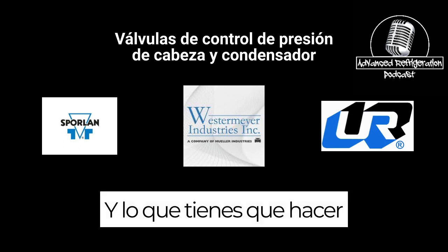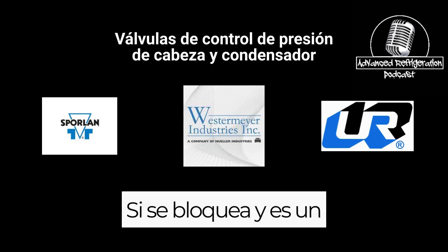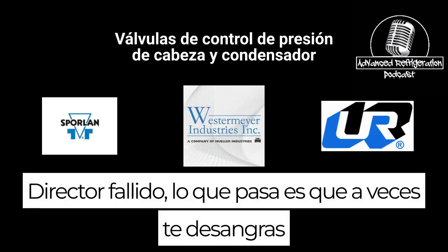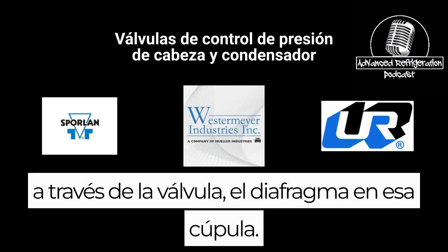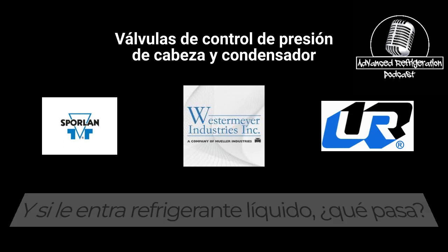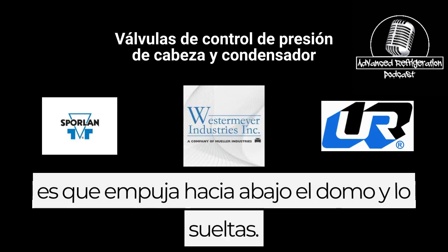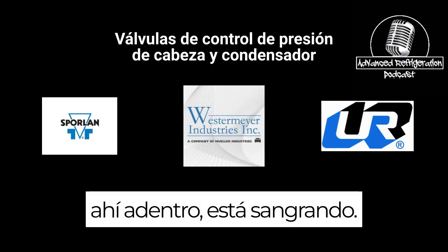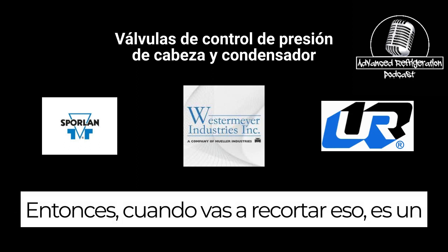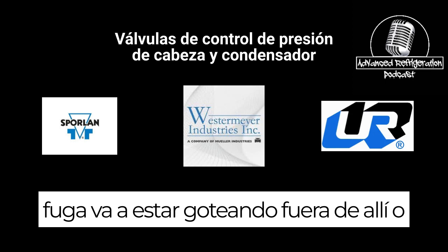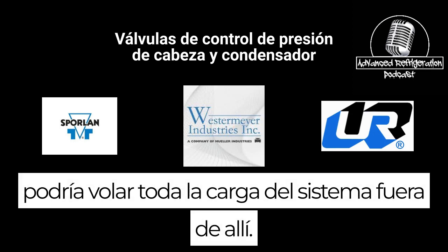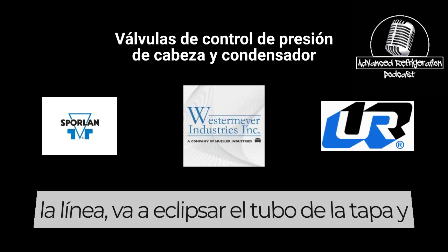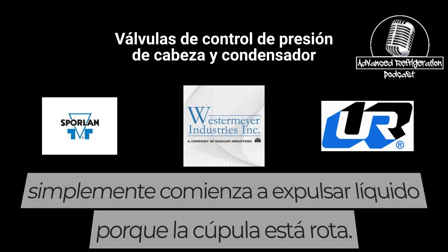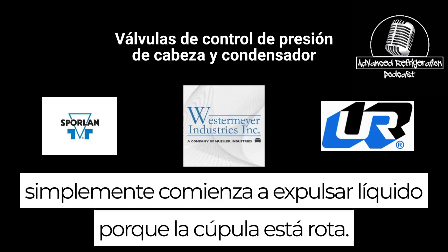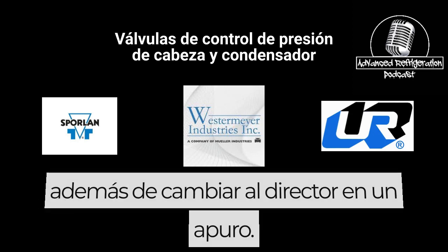Guys clip that. And the thing you've got to be mindful of, here's the issue. If it does lock up and it is a failed headmaster, sometimes you get bleed through from the valve, into the diaphragm, into that dome. And if you get liquid refrigerant in there, it pushes down on the dome, and if you release that, it's bleeding through. So when you go to clip that, it's going to be leaking out of there, and it could blow the entire system charge out. I've seen that happen when an apprentice goes and clips the cap tube and it just starts blowing liquid because the dome is ruptured. There's nothing you could do besides change the headmaster.